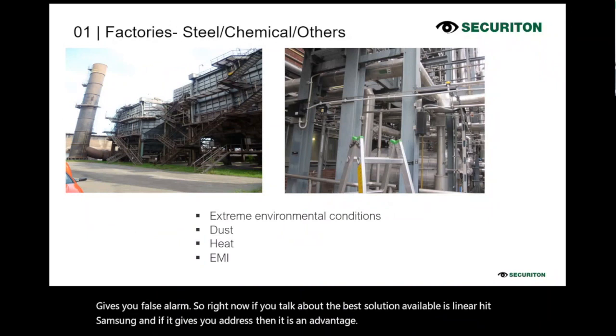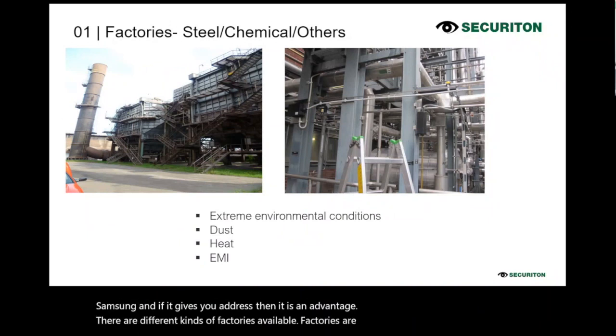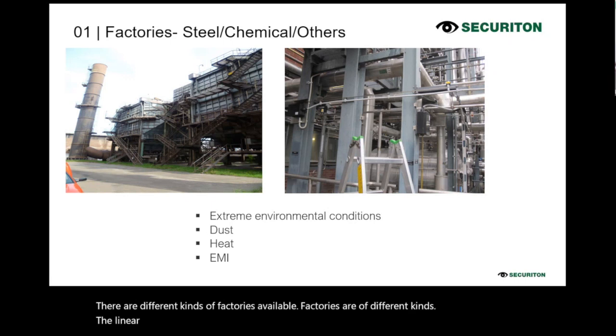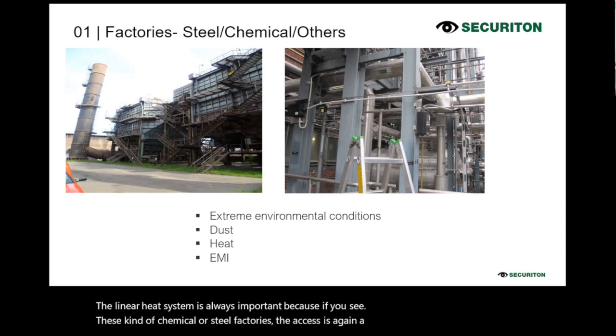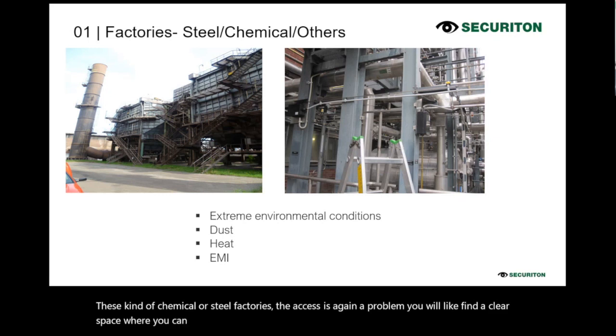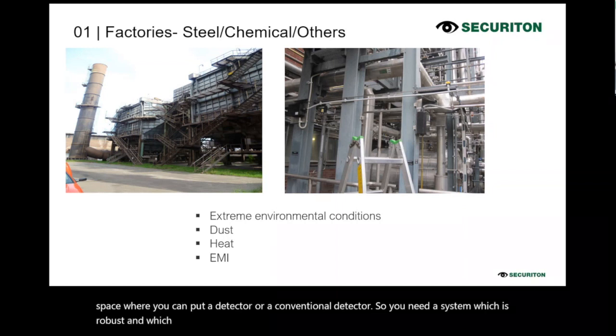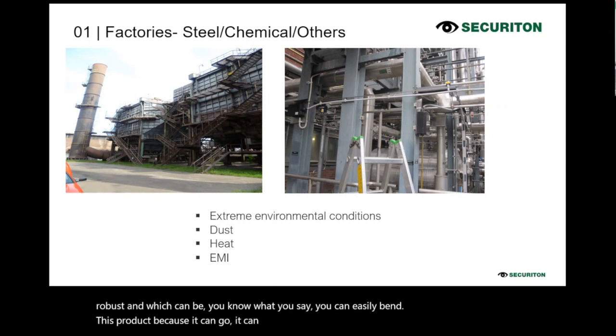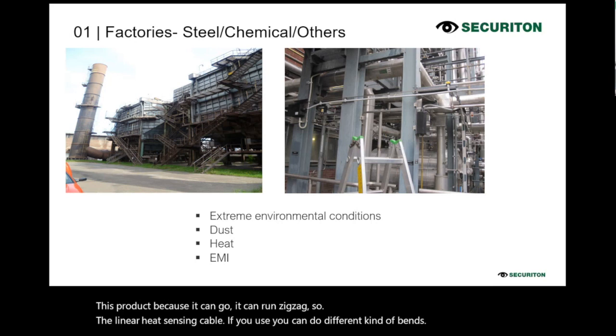There are different kinds of factories available. The linear heat system is always important because if you look at chemical or steel factories, access is again a problem. You will not find a clear space where you can put a detector or a conventional detector. So you need a system which is robust and which you can easily bend, because it can run zigzag. So if you use the linear heat sensing cable, you can make different kinds of bends and install it very accurately in this kind of environment.